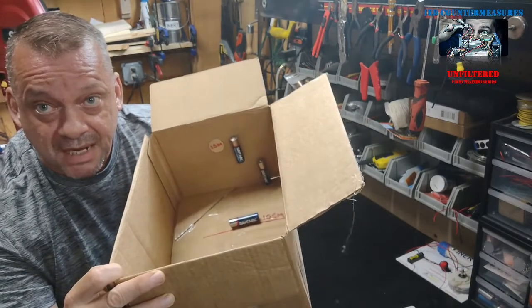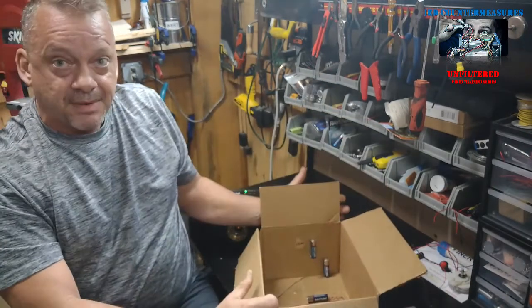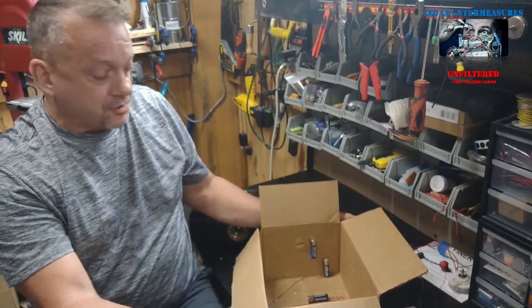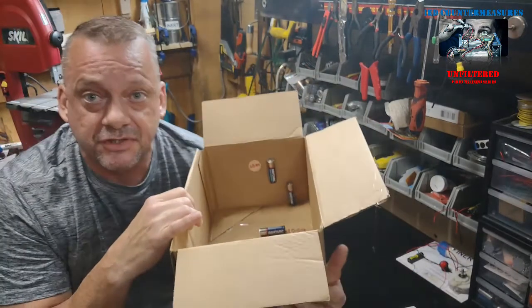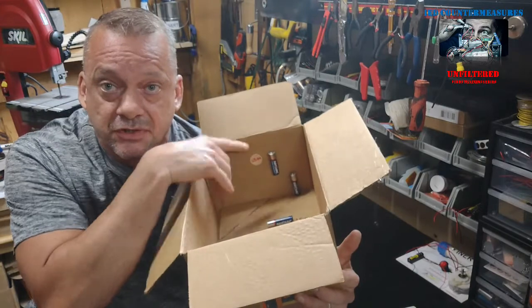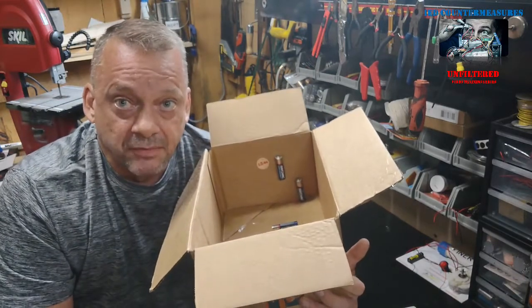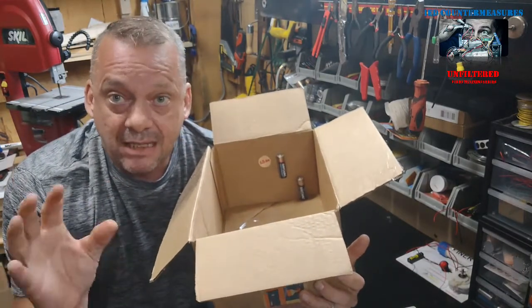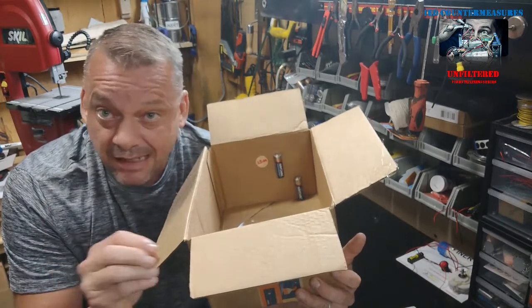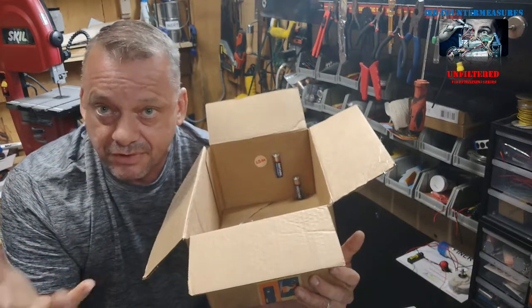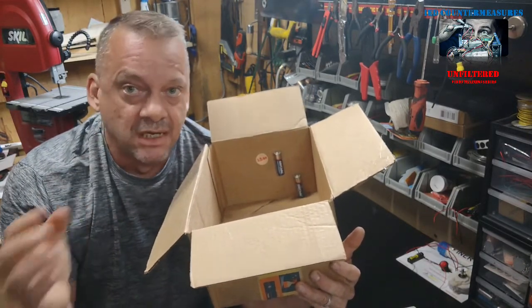So you'll shoot this box and you'll place it with this back end against your panel. You'll shoot this box, and the first thing you'll do is you go in your measurements and you'll measure this fiducial and put it in at 25 millimeters. Okay, bam. Now we've calibrated our measurement to an exact known fiducial. That's what a fiducial is. It's an exact known reference.